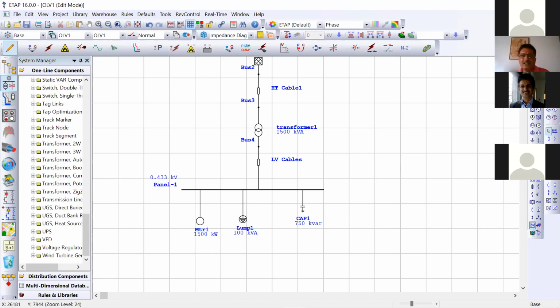Then, in continuation, an extension of this basic purpose will be to have relay coordination. So those modules are also available. Different relays are there which can be fixed by means of CTs. So I will take that. I will add this is a PT and this is a CT we have. I'll remove this, and I will connect a multifunctional relay.